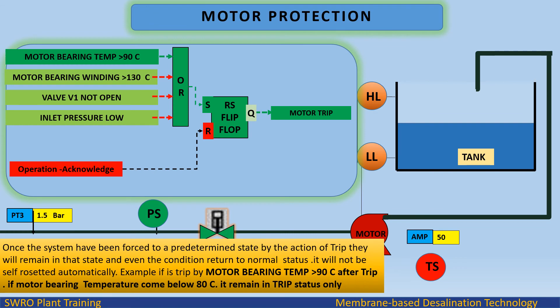Motor protection example: if motor bearing temperature exceeds 90 degrees, it sets the RS flip-flop and the motor trip output is activated. Once the system has been forced to a predetermined state by the action of a trip, it will remain in that state even if the condition returns to normal status — it will not self-reset automatically.